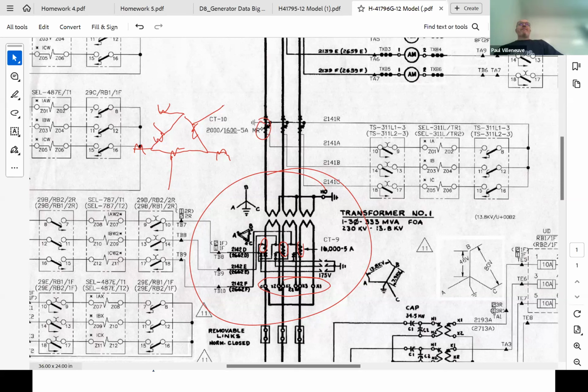The current transformers are buried inside what? They're buried in the transformer. This right here is the terminals - you can see X1, X2, X3, that's on the outside of the transformer. Then the wires go down into the individual transformers themselves, and they put CTs on those wires. So to access and replace those CTs, they have to take the transformer apart and get in there.